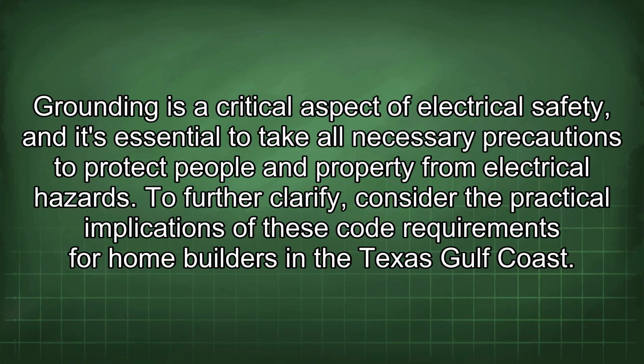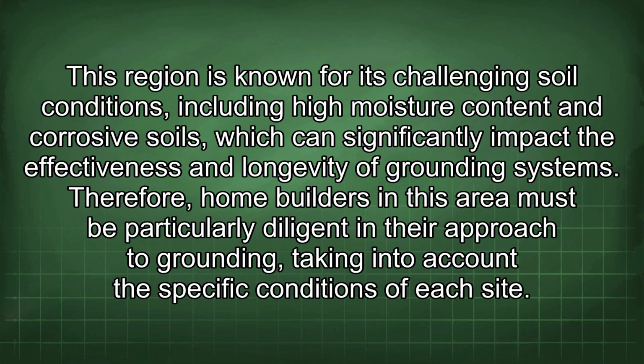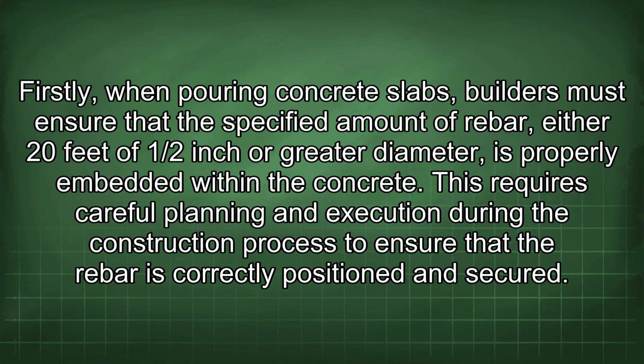Texas Gulf Coast. This region is known for its challenging soil conditions, including high moisture content and corrosive soils, which can significantly impact the effectiveness and longevity of grounding systems. Therefore, home builders in this area must be particularly diligent in their approach to grounding, taking into account the specific conditions of each site. Firstly, when pouring concrete slabs, builders must ensure that the specified amount of rebar, either 20 feet of 1/2 inch or greater diameter, is properly embedded within the concrete.